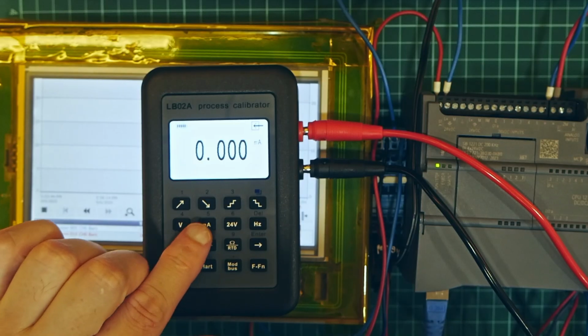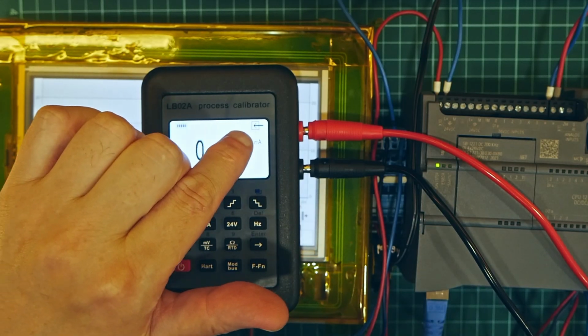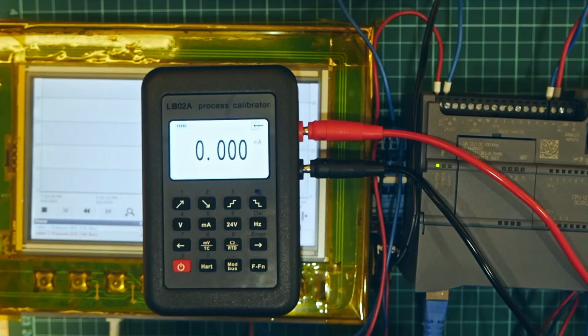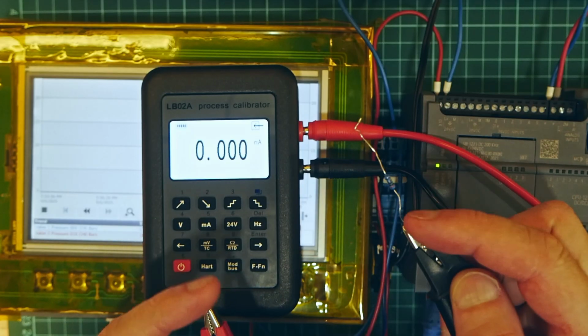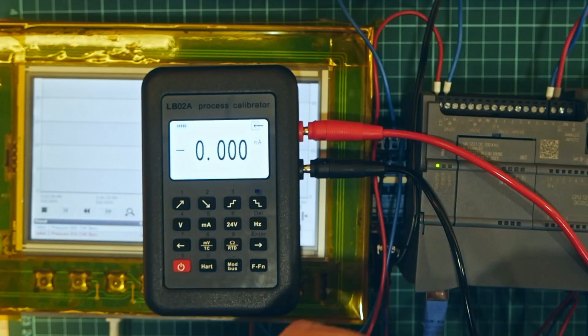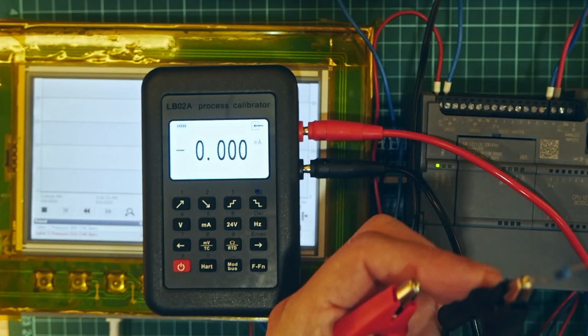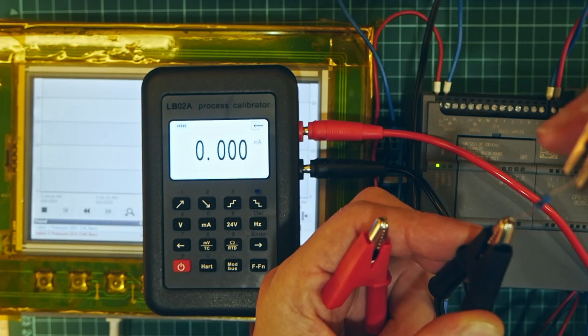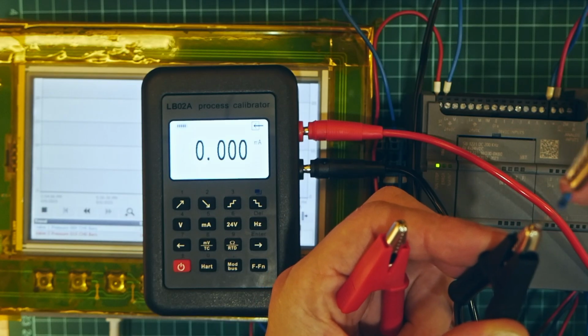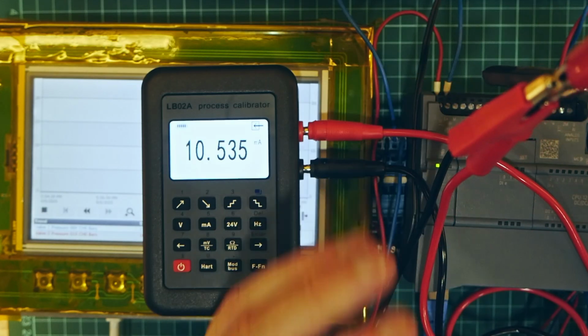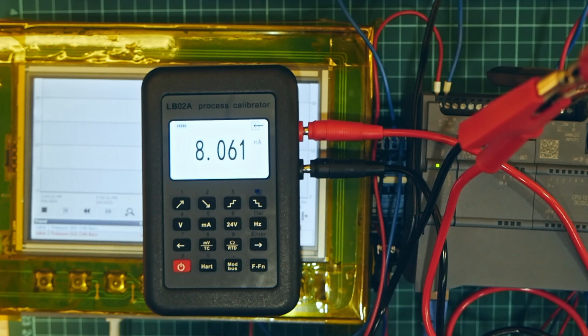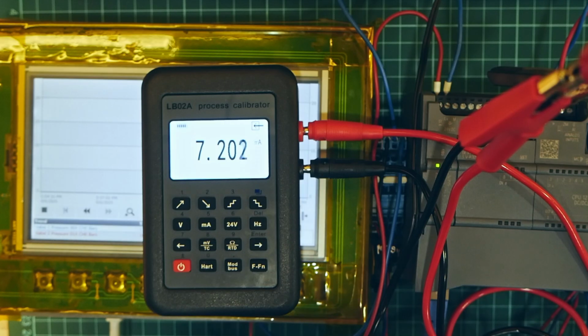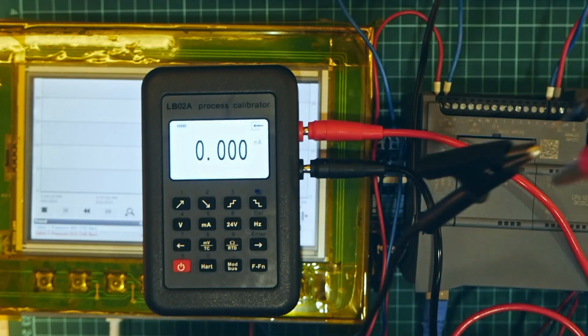Now we are in milliampere input mode. These crocodile wires, we don't have anything, we don't have voltage on these wires. Well, at this point I can only simulate something on my power supply. I provide from my power supply to... So you see, you can measure milliamperes. So let's say you have a sensor, it's drifting, it's not drifting, what kind of signal it gives. Yes? So you can check that.